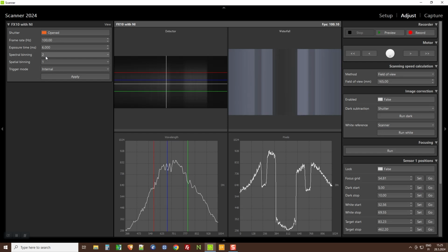You can also do that in the spatial direction. By default, this camera has 1024 spatial pixels. If you bin by 2, you will have effectively 512. The binning is important because it improves the signal-to-noise ratio by the square root of the binning factor. So here we have a binning of 2 times 1, and the square root of 2 is 1.4. So basically you can already improve the SNR of your data by 40% by doing that.